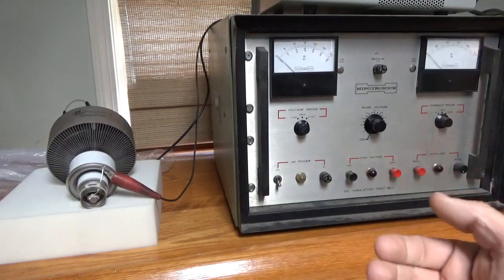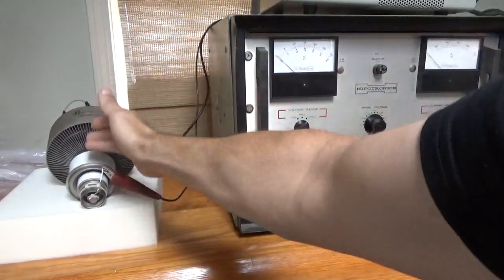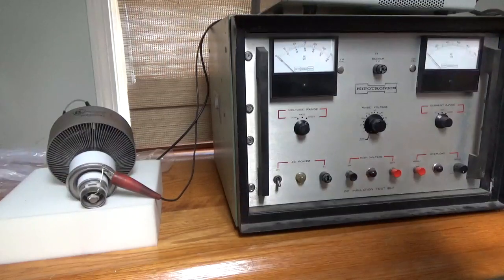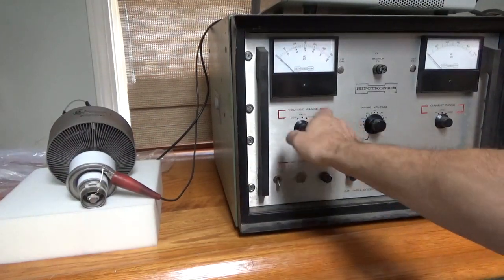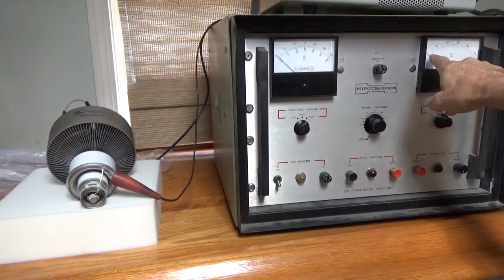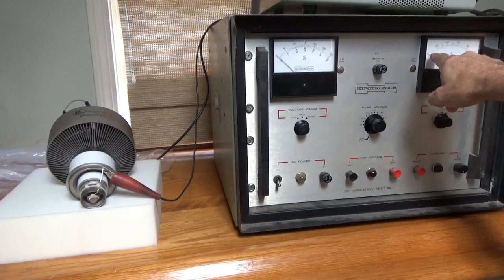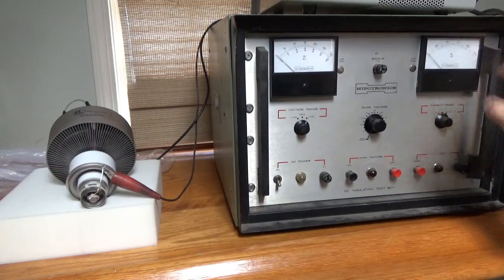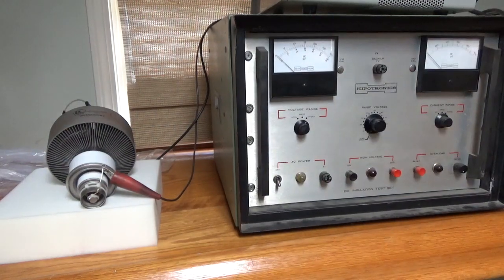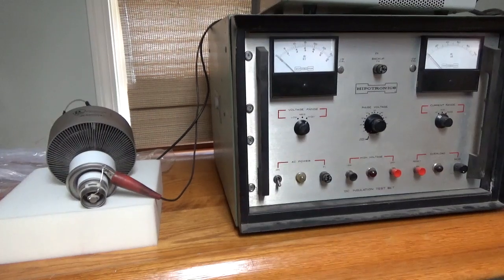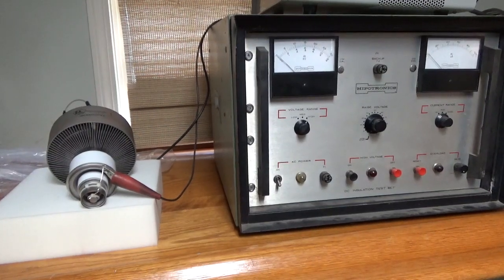So in this test, I'm going to test between the anode and the grid. I'm going to set the tester to the highest setting, so I should get it to 20kV DC. If I see the current meter starting to come up at all, if it comes up maybe a few lines and it progressively goes forward, I back it down, because that's indicating that an arc is starting to form.